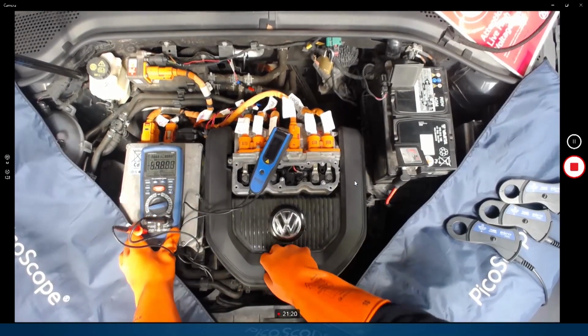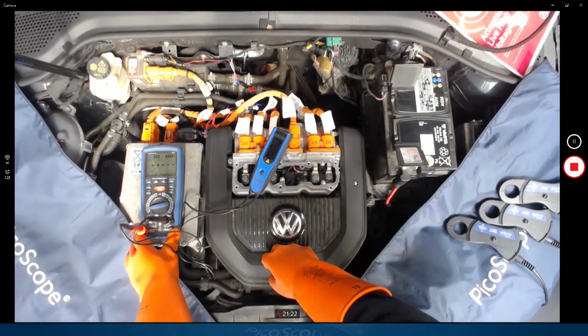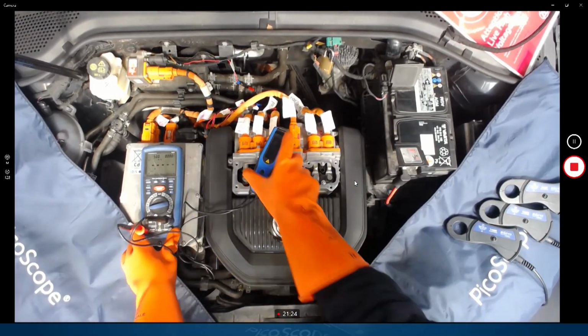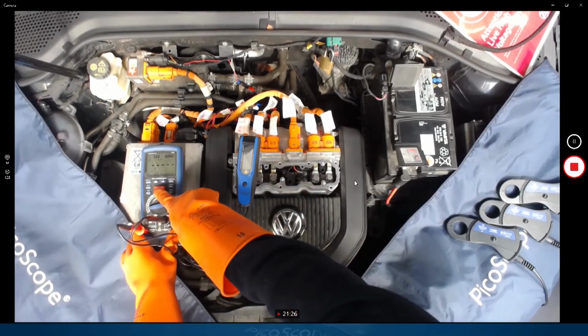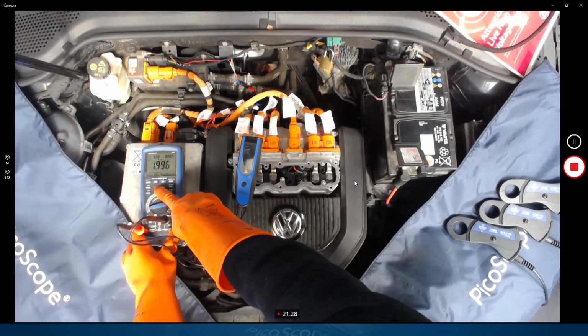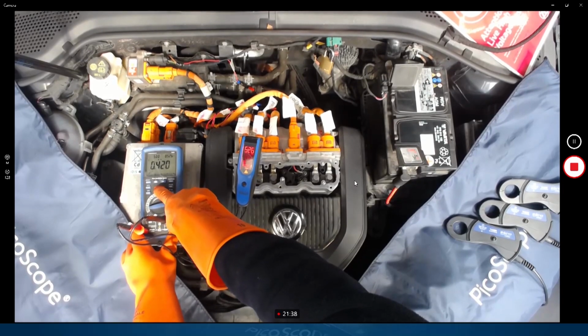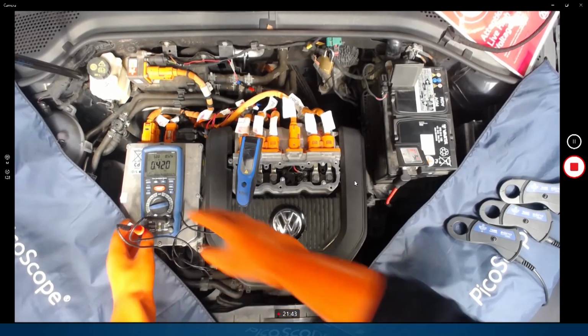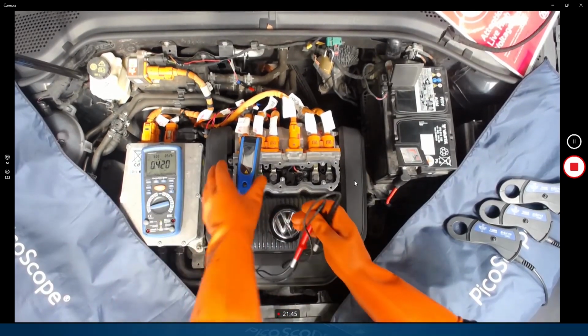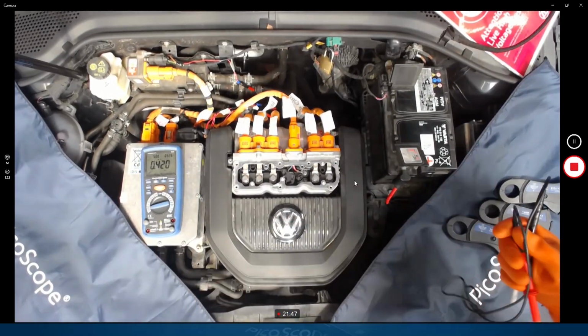We can set our insulation tester to its default of 500 volts. Now if I press the test button, this will start to output 500 volts. And there we go - our insulation tester is saying we have 526 volts, and our 2-pole tester is saying 526 volts, also measured as DC. That helps confirm the 2-pole tester is more than capable of detecting that higher voltage.